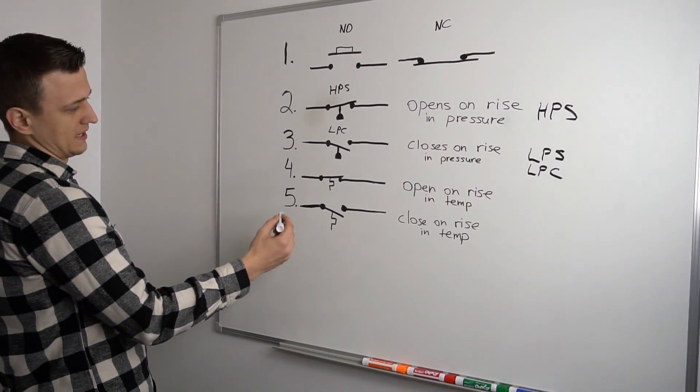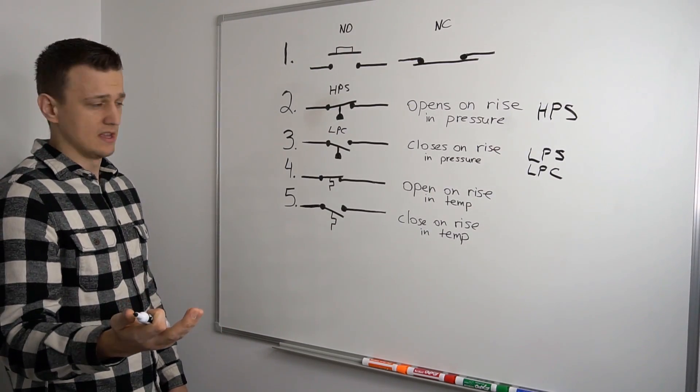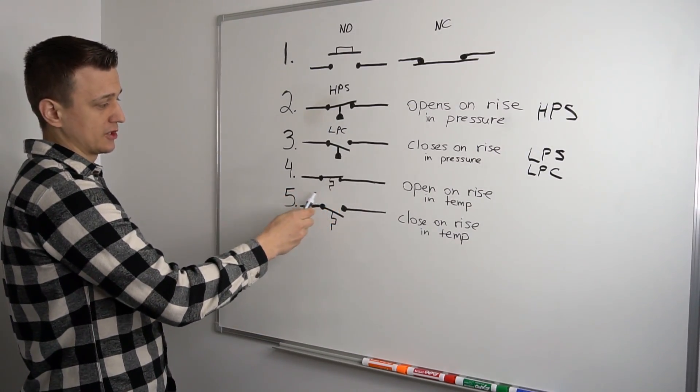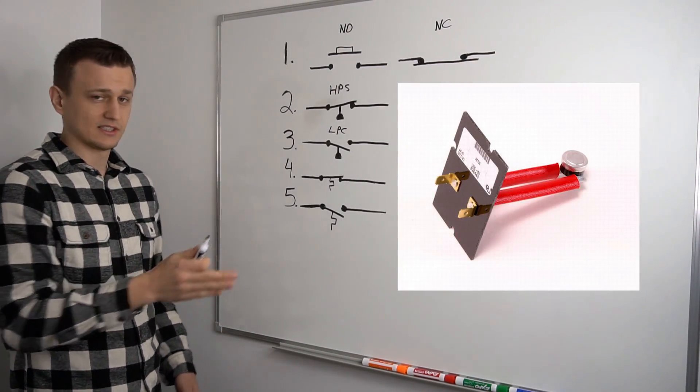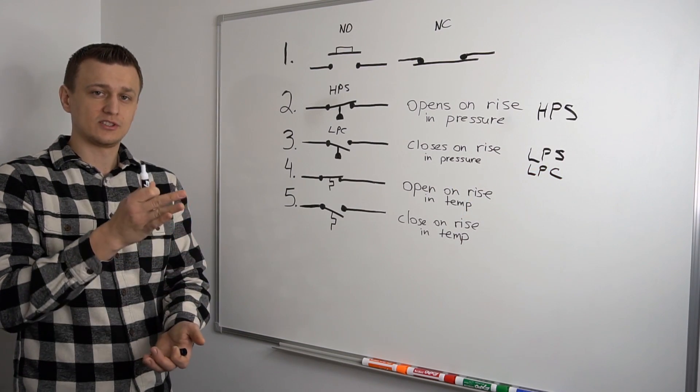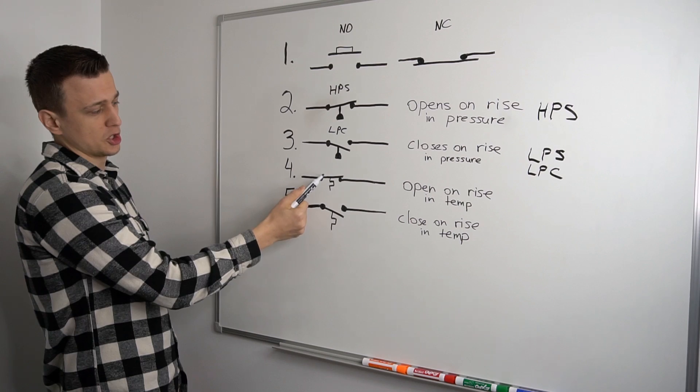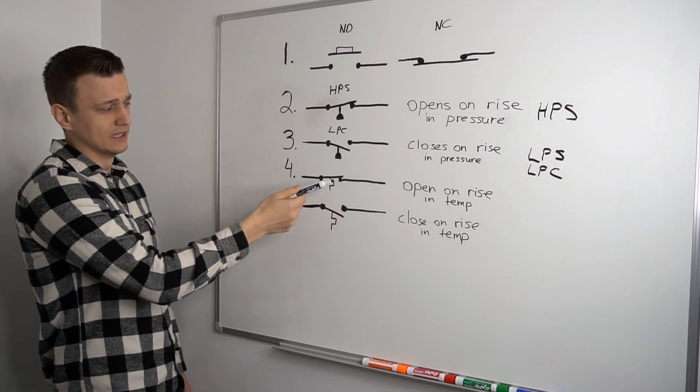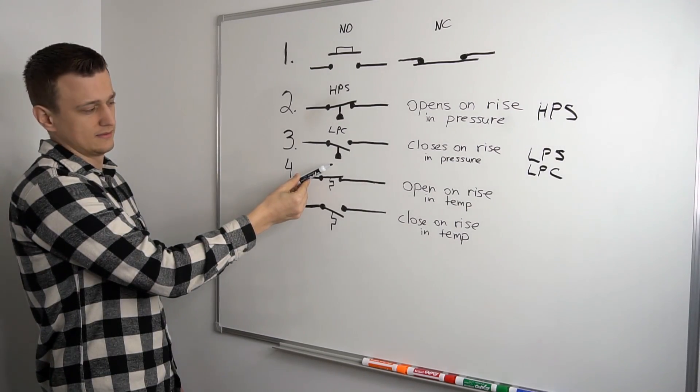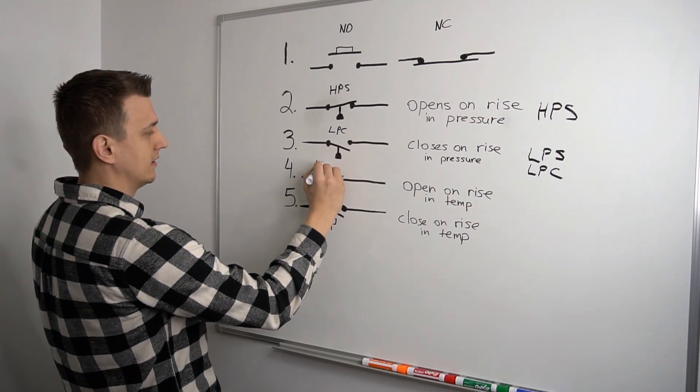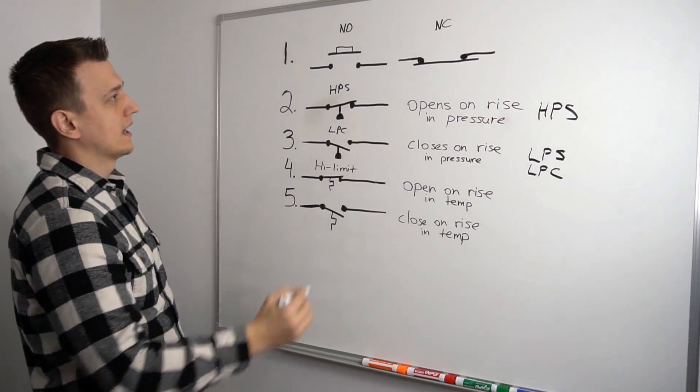And two examples of this would be, for example, either a flame rollout switch or a high limit switch on a furnace. So this is a normally closed switch on a furnace. Let's say the high limit, it's a normally closed switch. But if for some reason, let's say the filter hasn't been replaced for ages. The furnace starts to overheat. It gets too hot. The temperature goes up higher than it should, whatever the rating is, like 160, 170. That goes up and interrupts the circuit if the furnace is getting too hot. And actually, let's write that down. So this would be the high limit, for example.